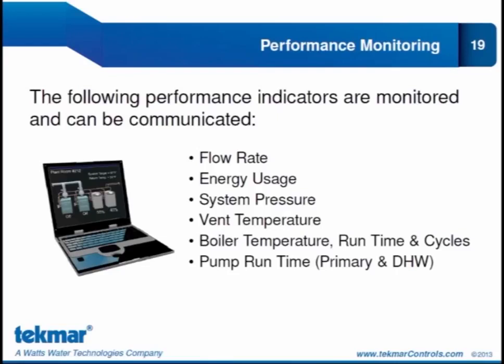If we have a pressure sensor in our system, then we can measure pressure and communicate that to the BAS. The pressure sensor would be a 4 to 20 milliamp pressure transducer, and we measure pressure in PSI or kilopascals. We talked about that vent sensor before, so we can measure the vent temperature and communicate that to the BAS. Ones that you would expect are the boiler temperature, boiler runtime, and cycles. And because we have the boiler inlet sensor and individual boiler outlet sensors, we can communicate individual boiler information as well as the boiler delta T. We can also communicate the runtime for the pumps, and that includes the primary pump and the domestic hot water pump.